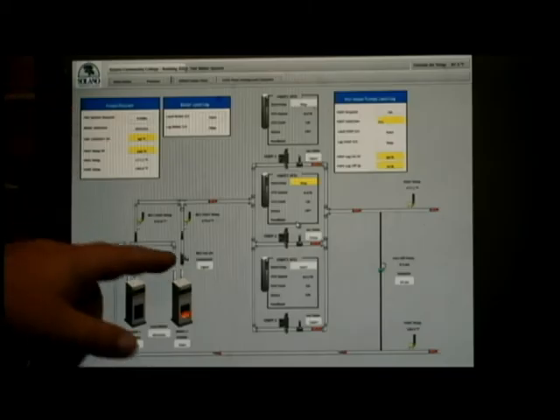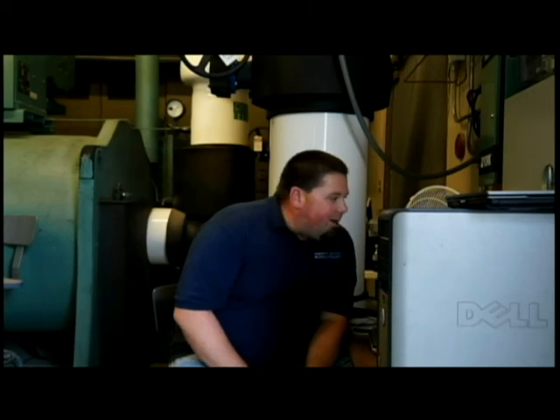Then the boiler selection is just the selector box that actually spells out boiler one or boiler two. Currently, boiler two is our lead. And then that boiler's ISO valve is opened up. That boiler is given a start command, and we currently have a set point of 185 degrees on that hot water loop and that boiler right now.